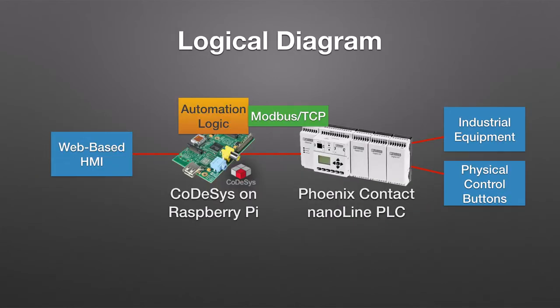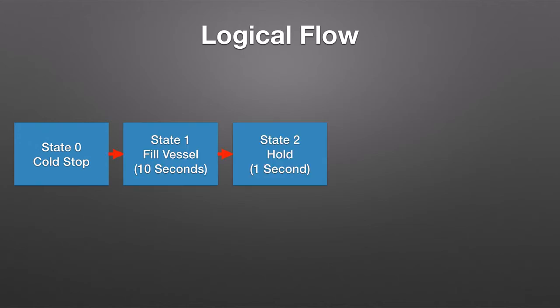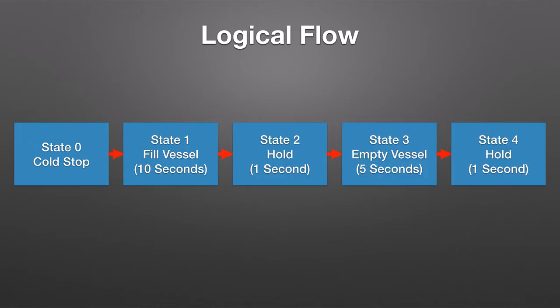This PLC is controlled directly over the network by Modbus commands from the CoDeSys controller, which runs the logic that drives everything. The logical flow configured for this system consists of six states: a cold stop, the filling of the vessel, a short hold, the emptying of the vessel, and another hold.